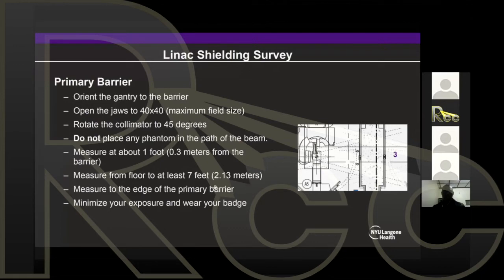And it's important to measure the edge of the primary barrier. So this setup doesn't work for secondary barriers. So you cannot measure both, just measure primary and then come here and measure secondary, because you need to change the setup. But you should actually go to the edge and make sure you have a sharp decrease. You need to make sure that you are really covering with your primary barrier what you should be covering.